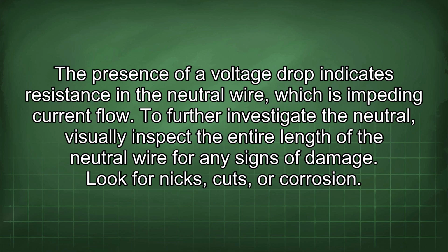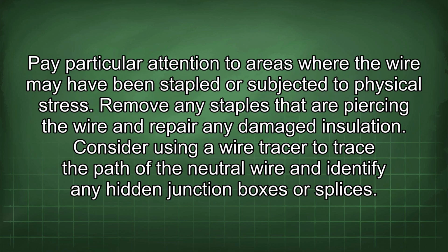To further investigate the neutral, visually inspect the entire length of the neutral wire for any signs of damage. Look for nicks, cuts, or corrosion. Pay particular attention to areas where the wire may have been stapled or subjected to physical stress.